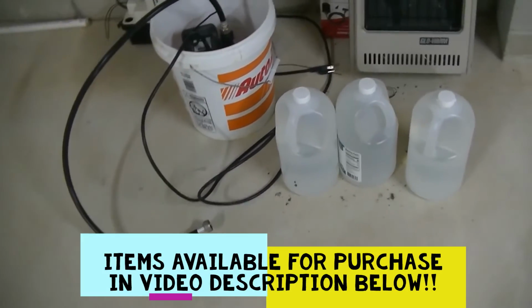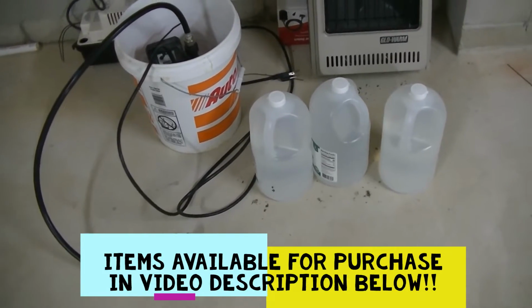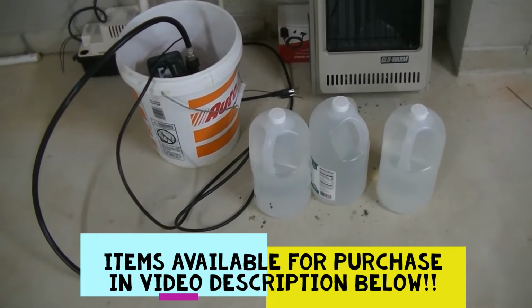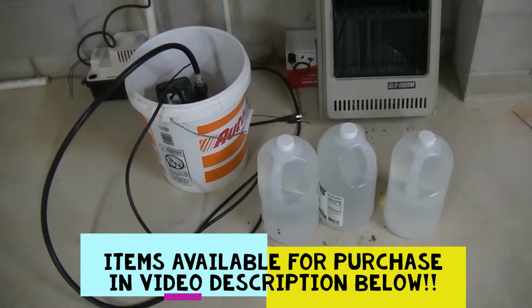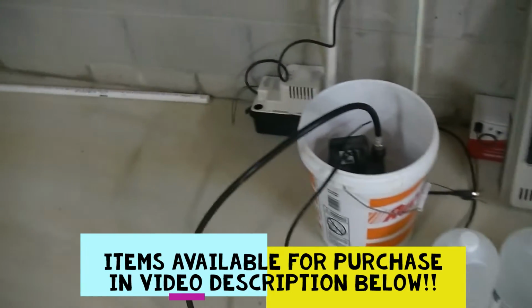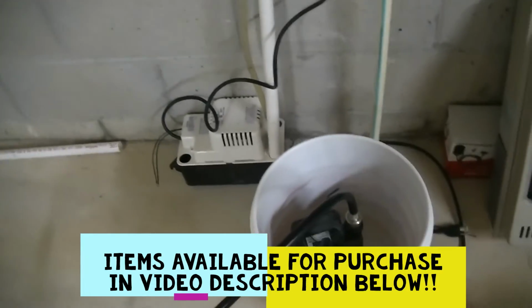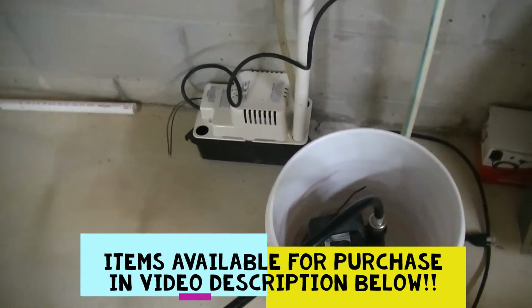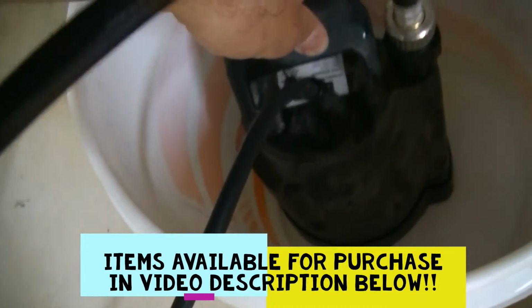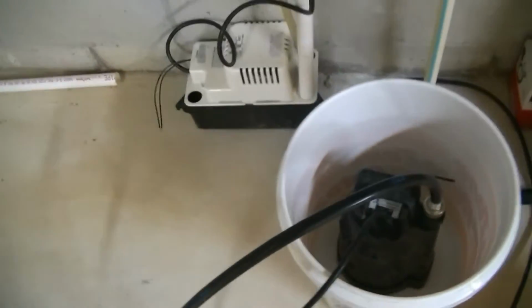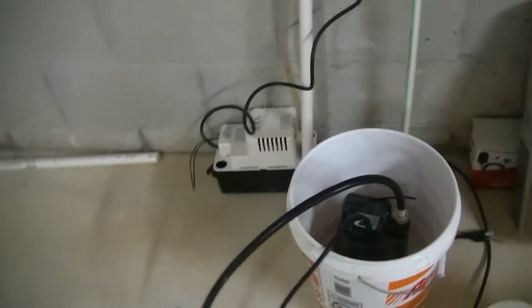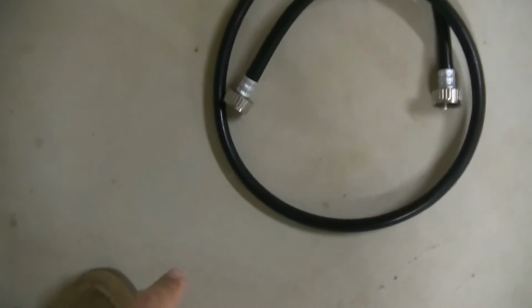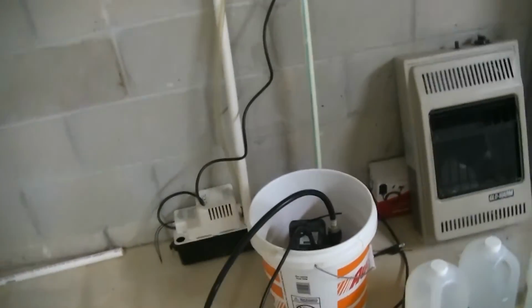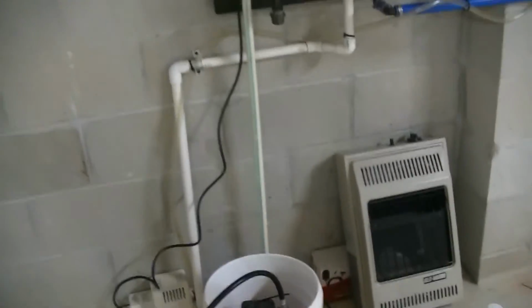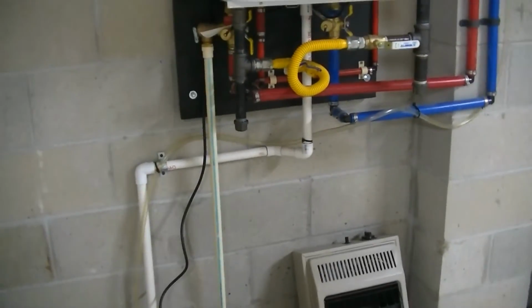Before I put you on the tripod, some of the things you're going to need: at least 2 gallons of vinegar—we have 3 here, we'll put 2 in there and see how it goes. You're also going to need some sort of universal utility pump; we have this 1/6 horsepower Utilitech here. And you're going to need a set of washing machine hoses—one here and one here. This is going to allow us to circulate the white vinegar through the heat exchanger to clean it out.